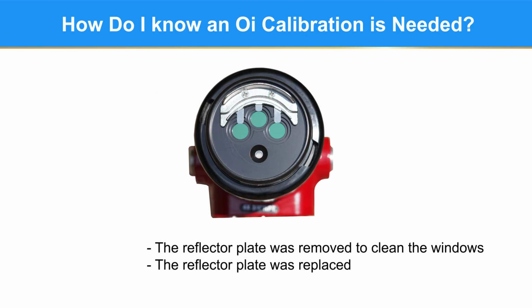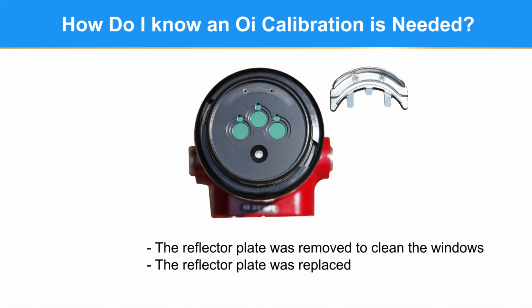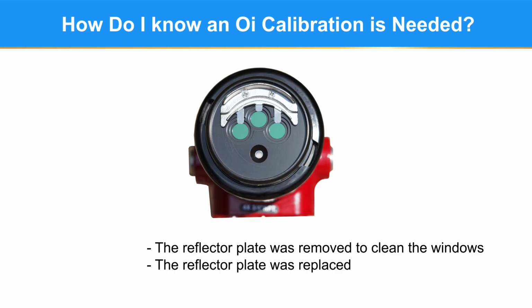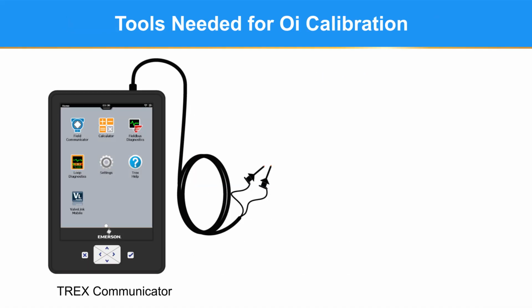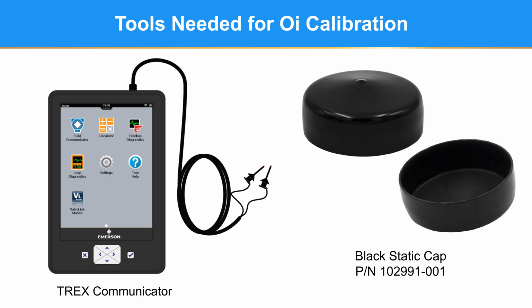And the third scenario is that the reflector plate was removed during the cleaning process, or the reflector plate was replaced. The tools needed for an OI calibration are a HART communicator and a black cap used to block out any infrared energy during the OI calibration.